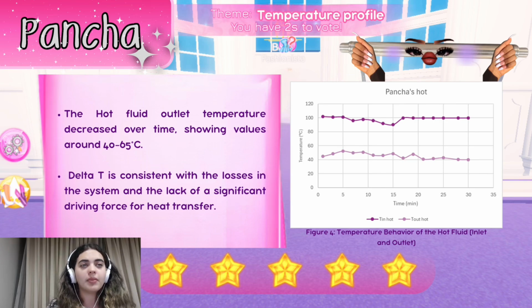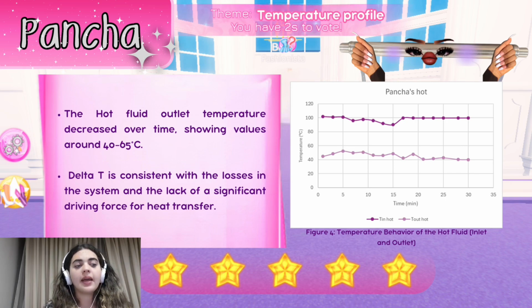I think the main problems were inconsistent inlet temperatures of the cold fluid, which reduced the driving force for heat transfer, and significant heat losses to the environment. This results, for example, in a small delta T for both of the fluids and poor overall performance. Finally, improving the insulation and stabilizing the cold fluid inlet temperature could significantly improve Pancha's efficiency. Welcome to our simulator.